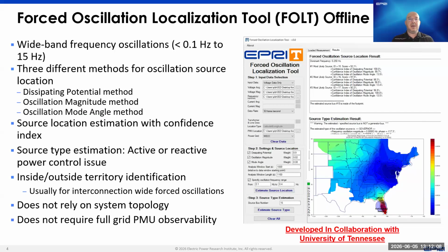As I said, one of the tools we used was EPRI's forced oscillation localization tool, FOLT. This has been developed in collaboration with the University of Tennessee. Because this is ongoing work where we keep adding features year by year, the version we used was one that can process PMU data. So we can analyze oscillations with frequency from low values, less than 0.1 hertz, up to 15 hertz or so. You've seen presentations in this task force that for higher frequency oscillations, PMUs have limitations. That's why we say up to 15 hertz. That's a reasonable frequency range where PMU data can be useful.